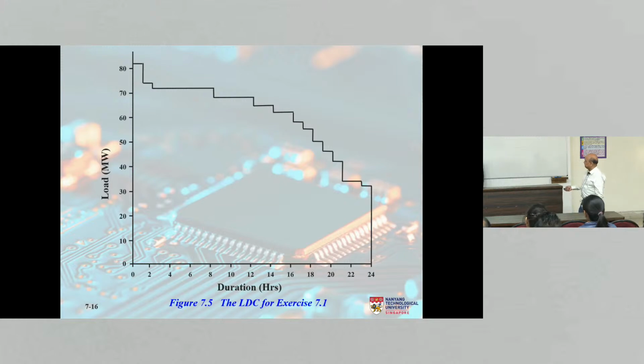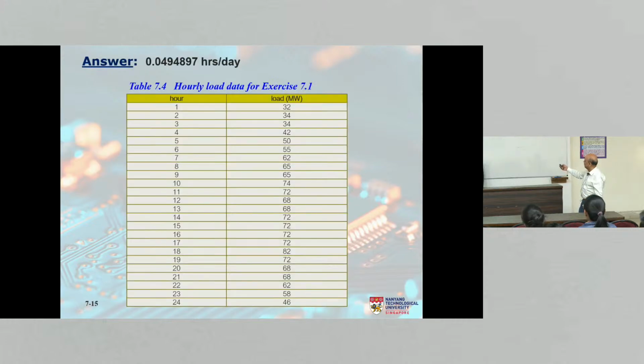Yeah. And if your load is 82 and the installed capacity is 100, so you are somewhere here, right? So if one generator goes out, 25 megawatt, you only have 75. You're going to lose load, correct? So how many hours are you going to lose load? You can just go here, you'll find it is 1 hour or 2 hours. And then you do LOLE equals the sum of p_k times t_k. That's it, very simple. I've given you the answer. It shouldn't be a problem, 0.049 hours per day.